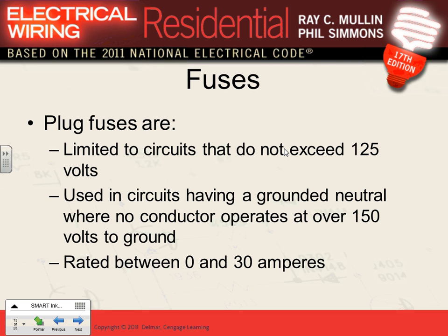Compared to this guy, this can only interrupt 10,000 amps, 10 kilo amps, versus 200 kilo amps. Can you guys see the difference? They can come lower. Typically 200 is the highest they can get. So your fuses come with voltage limitations. There are smaller fuses, guys. They rate these plug-in fuses up to 120 volt, single-phase.